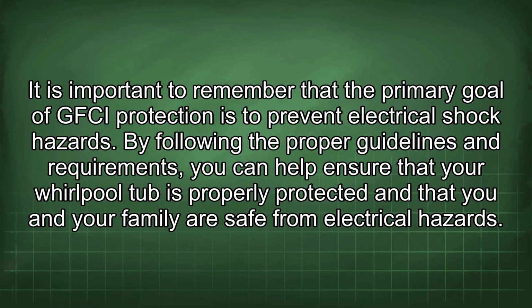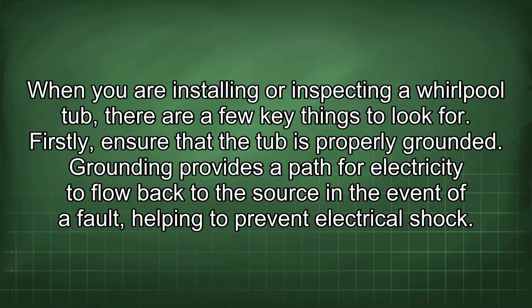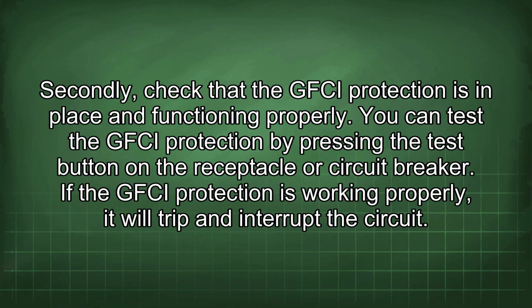It is important to remember that the primary goal of GFCI protection is to prevent electrical shock hazards. By following the proper guidelines and requirements, you can help ensure that your Whirlpool tub is properly protected and that you and your family are safe from electrical hazards. When you are installing or inspecting a Whirlpool tub, there are a few key things to look for. Firstly, ensure that the tub is properly grounded. Grounding provides a path for electricity to flow back to the source in the event of a fault, helping to prevent electrical shock. Secondly, check that the GFCI protection is in place and functioning properly.